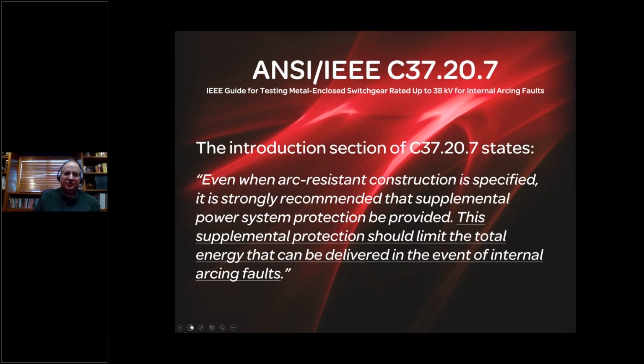So the introduction section, right at the beginning of C37.20.7, says, when arc-resistant construction is specified, it's strongly recommended that supplemental power protection be provided. Let's be clear here. What is this saying? It's saying even when you have arc-resistant construction, supplemental power system protection is recommended. This supplemental protection should limit the total energy that can be delivered in the event of a internal arcing fault. This is my impression of C37.20.7, I'm giving you a singular interpretation here: it was written with arc venting, mechanical venting in mind. Because they know that mechanical venting doesn't reduce incident energy at all. So they're recommending that additional arc flash mitigation be applied to reduce incident energy, even when you have mechanical venting.